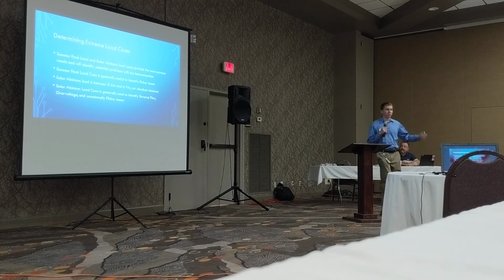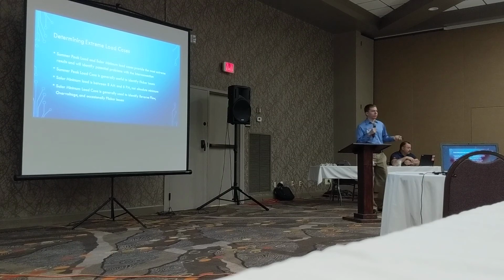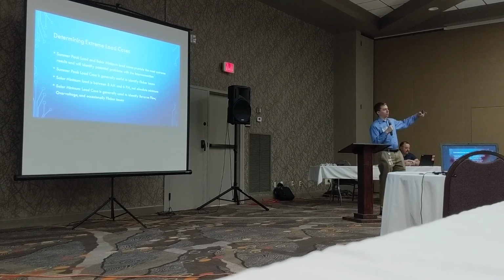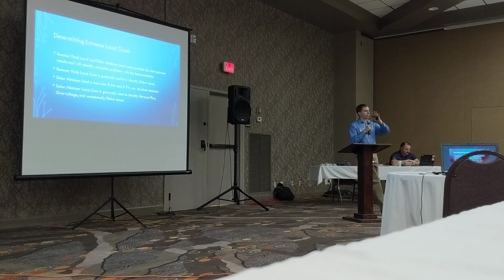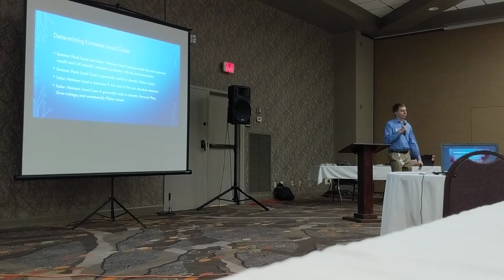So we've determined our extreme load cases. Again, summer peak and what's called solar minimum to identify the potential problems. At the extreme cases, that's when you find out what the problems are. Summer peak is mostly for flicker issues because you've got a lot more voltage drop because you've got more load. So your currents are higher. The further out you go, the lower your voltage gets. If you throw a generator up there, it improves your voltage. But if it drops offline, then your voltage swing is a lot higher because there's a lot more drop than there was before. So that's what we look at in the peak case.